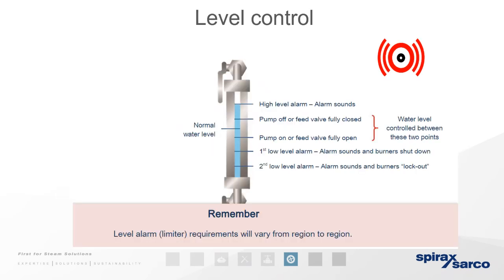We should be able to identify all the boiler states and conditions by observing the sight glass or gauge glass. But this only gives us a visual indication. We need to install level controls, control probes that are capable of monitoring the true water level. Because the glass sits on the side of a boiler, it will show a level, but it relies on it being clean, being blown down properly, and all those things. So we would still recommend that you have the probes. I think it's a legal requirement, the probes inside the boiler to give you your alarms.